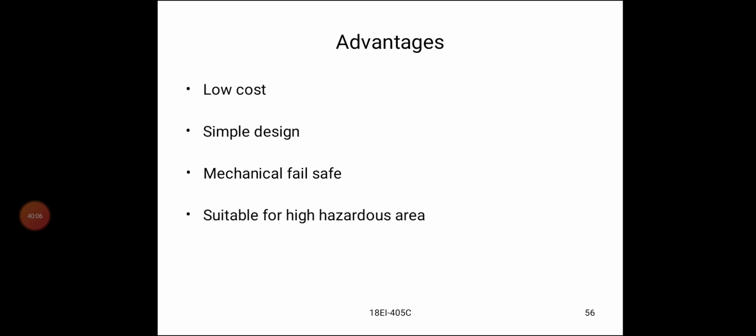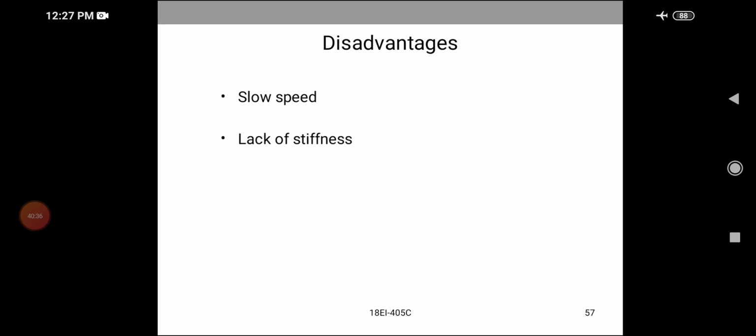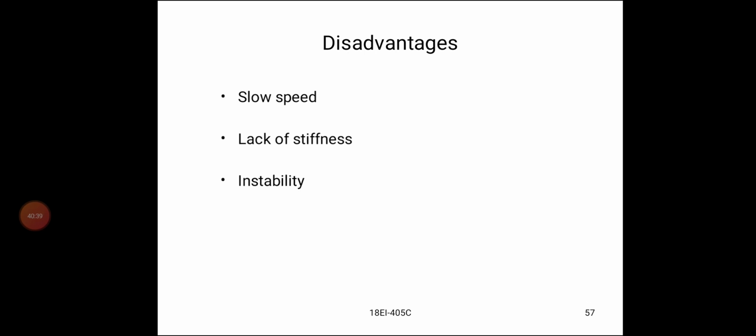Inlet pressure. It is a simple design, mechanical fail-safe and suitable for highly hazardous areas. There are no electrical signals, so it is safe and suitable for highly hazardous areas. Disadvantages: slow speed, lack of stiffness, instability, moderate thrust.